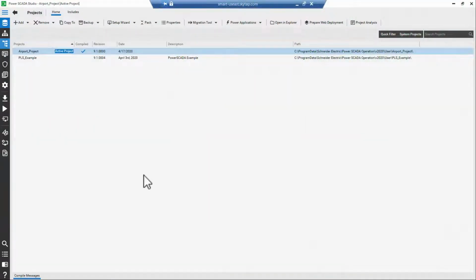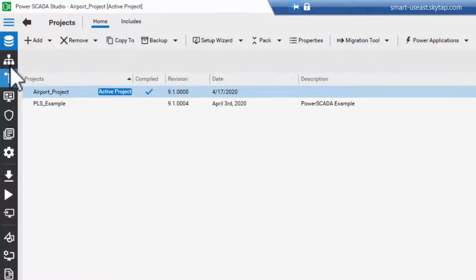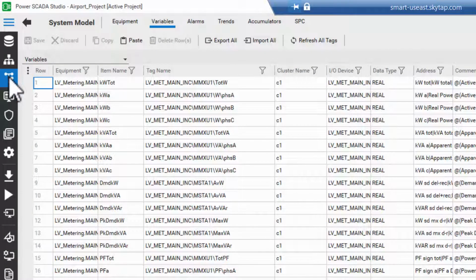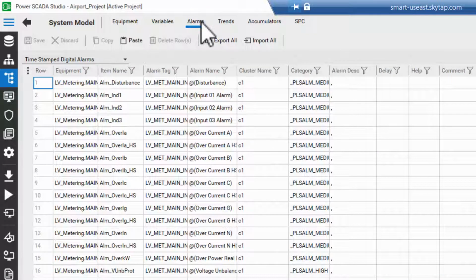The most basic connection between the WebHMI graphics and the runtime engine is the item binding. Each tag that I want to display on a diagram has an associated item name. We discuss creating these items in more depth in the Profile Editor videos. Beyond the variable tags, I can also bind alarm statuses to the graphics so long as they have item names assigned.